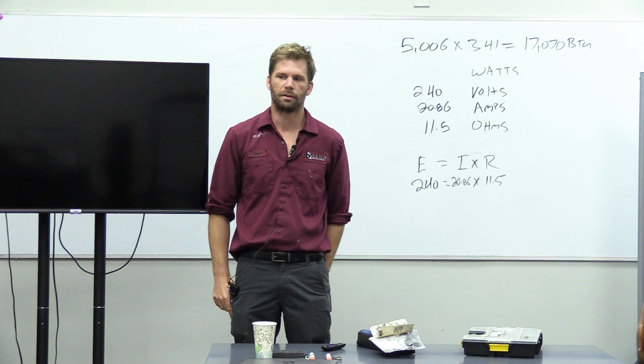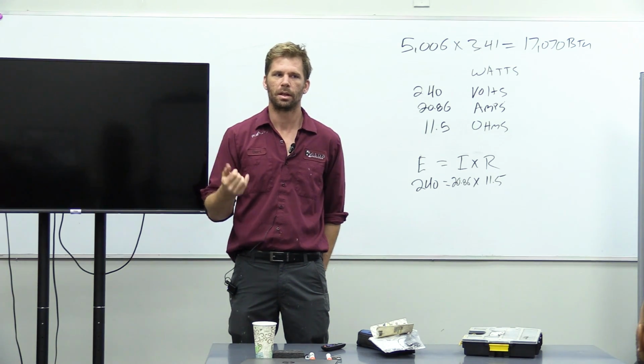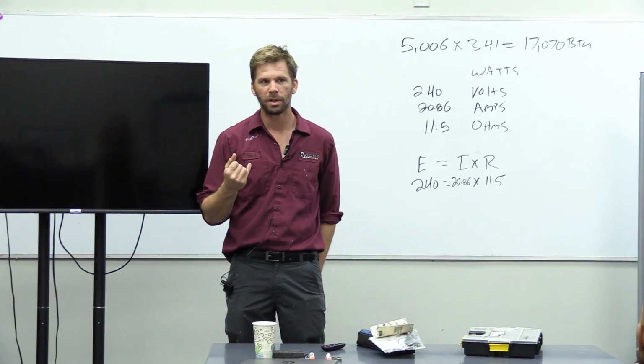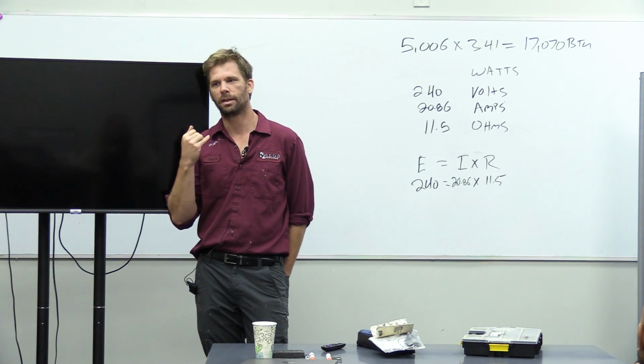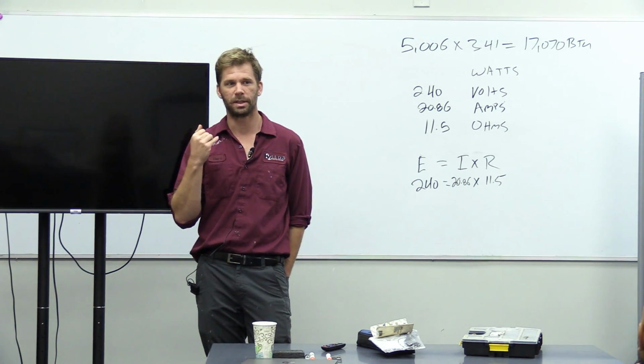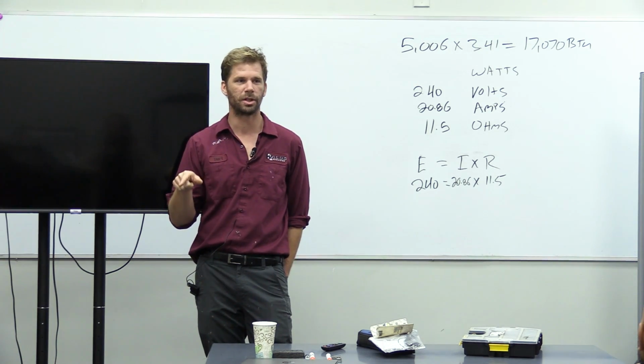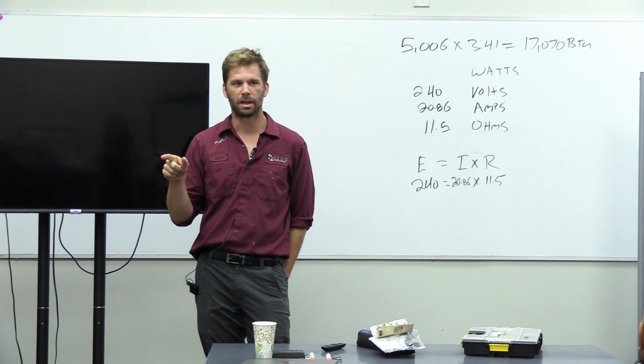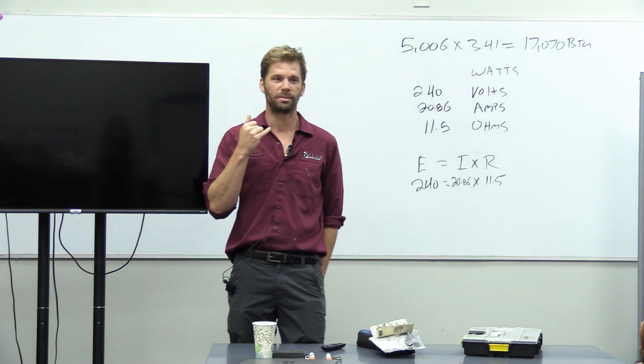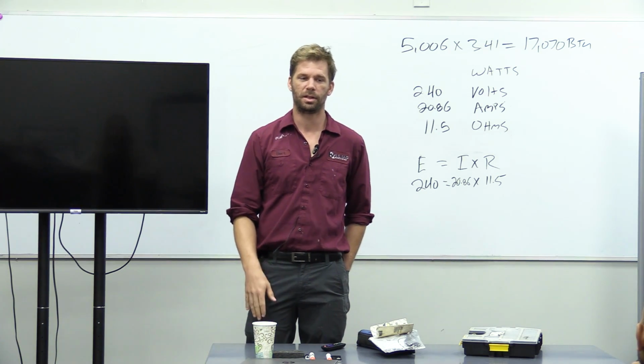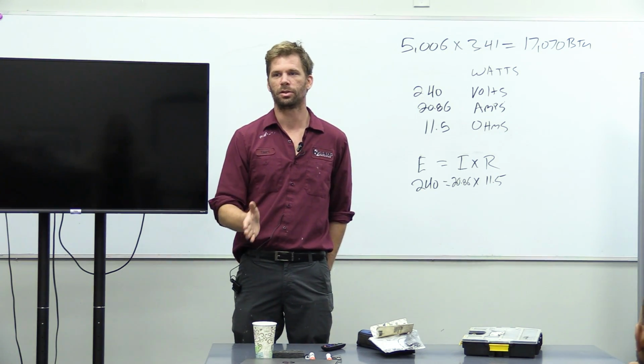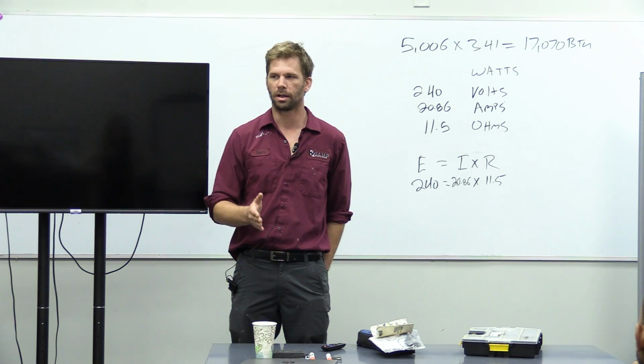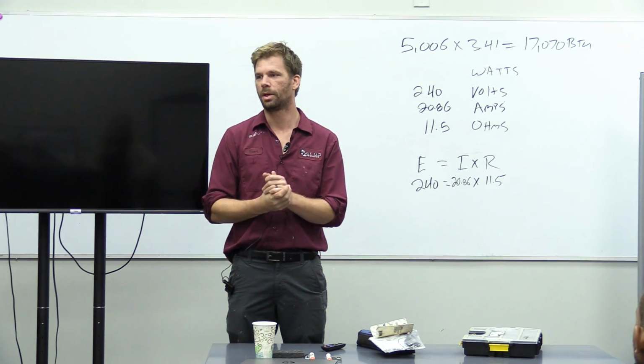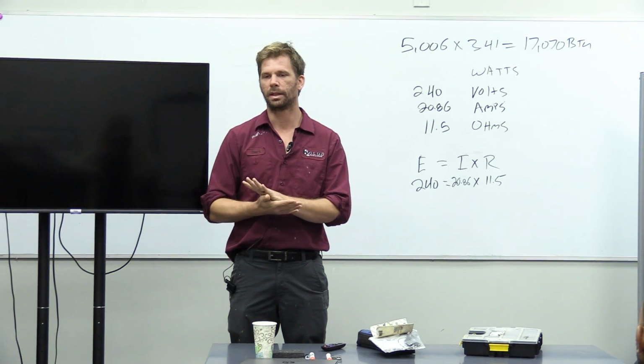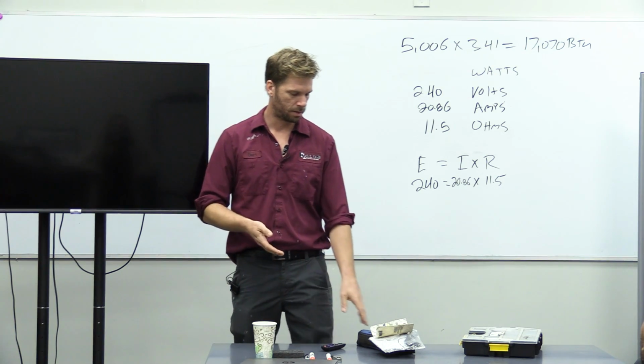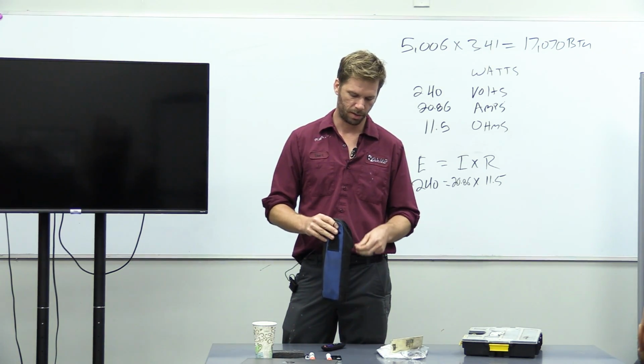Even in installing, you're going to find that you put in a new heater, you call the customer, new heater's in, okay, turn it on, guests are coming tomorrow, we need that pool heated. And it's like, well, it's 42 degrees right now, I'll turn this heater on, it'll run for about 4 hours until your pump timer shuts off. Then in the morning it'll come back on, but it's probably going to be 2 days before your pool gets warm, with this kind of weather. They need to know. They just got a brand new heater, so set the expectation straight. Just because it's brand new doesn't mean it's going to heat really fast as a heat pump on a cold day. And I think I mentioned before, but this is what I use for testing the water temperature difference.